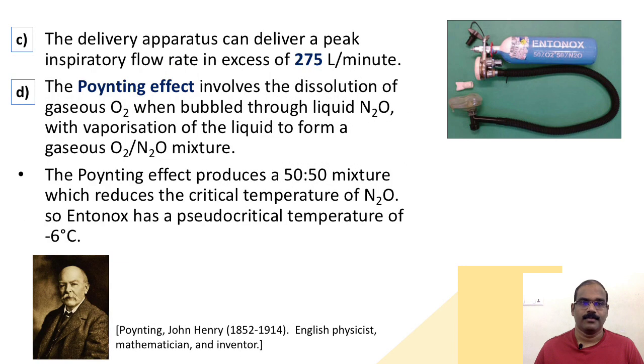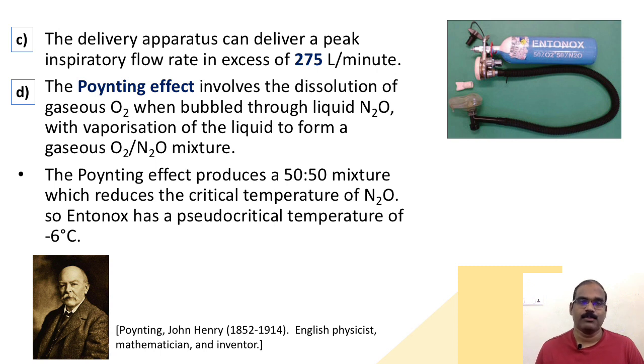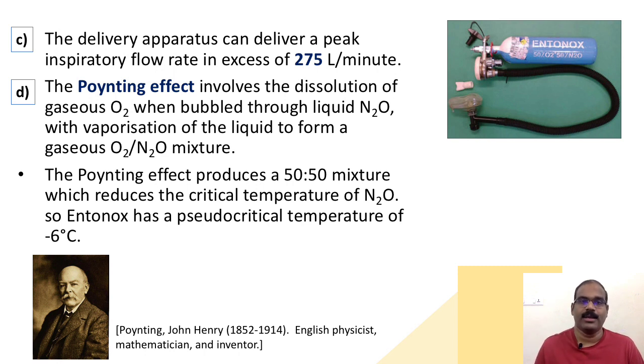The third part was about the peak inspiratory flow rate supported by the delivery apparatus — it supports in excess of 275 liters per minute. The fourth sub-question was about the Poynting effect, which involves the dissolution of gaseous oxygen when bubbled through liquid nitrous oxide with vaporization of the liquid to form a gaseous oxygen-nitrous oxide mixture. The Poynting effect produces a 50/50 mixture, which reduces the critical temperature of nitrous oxide.